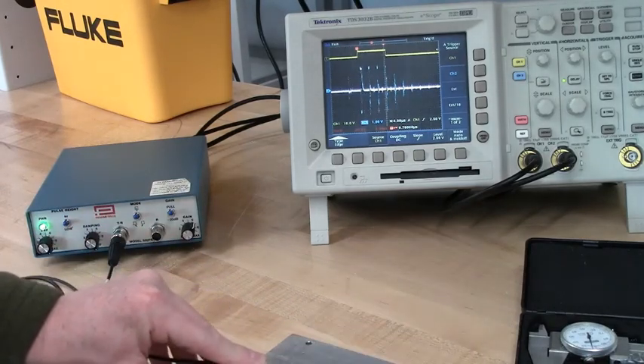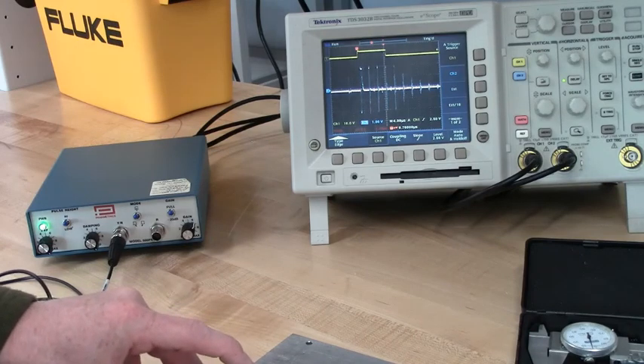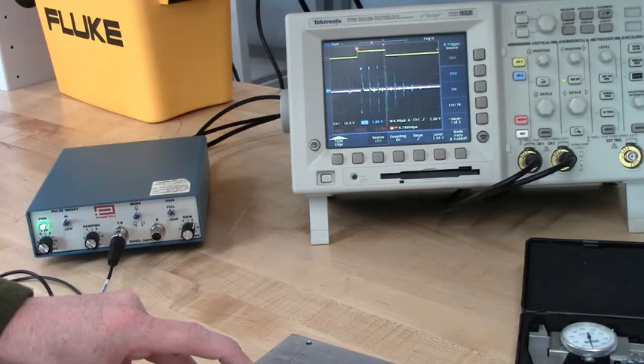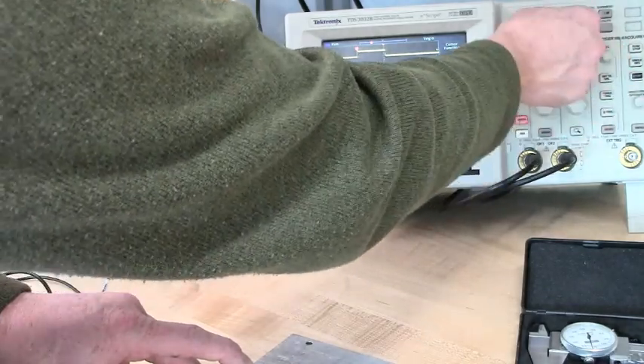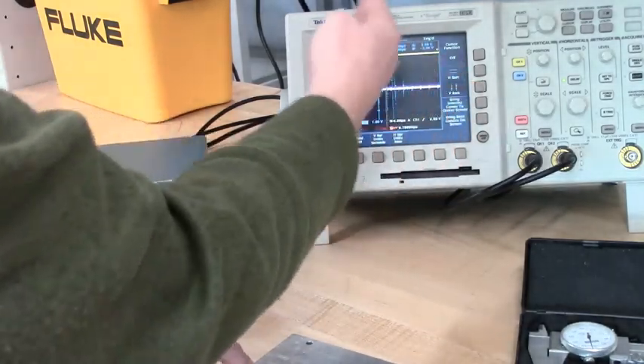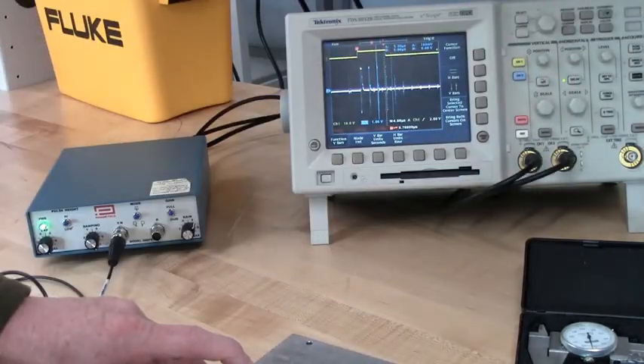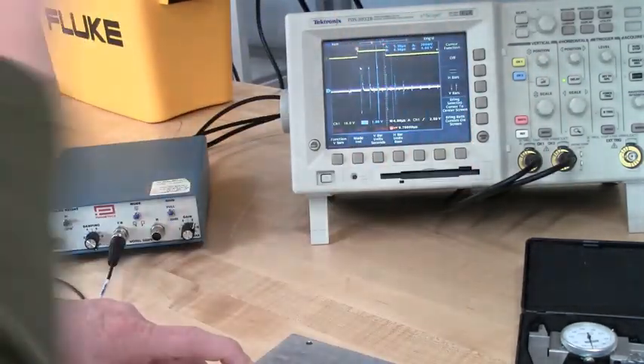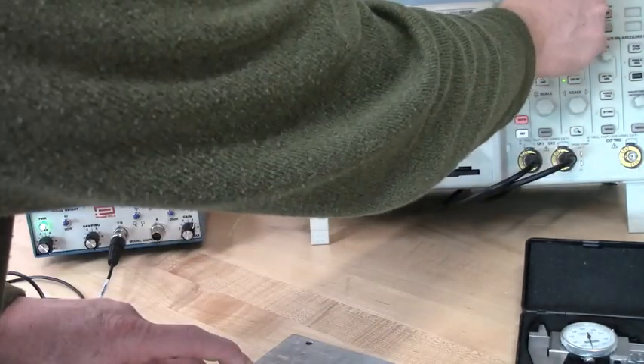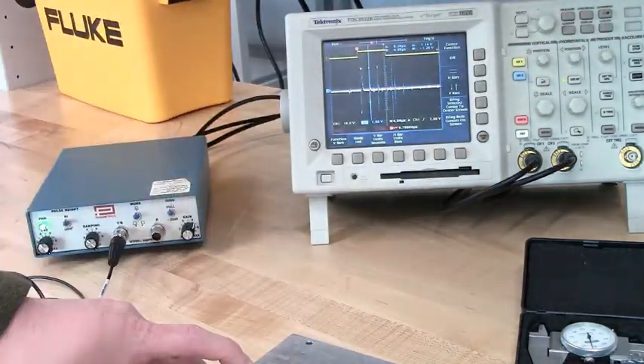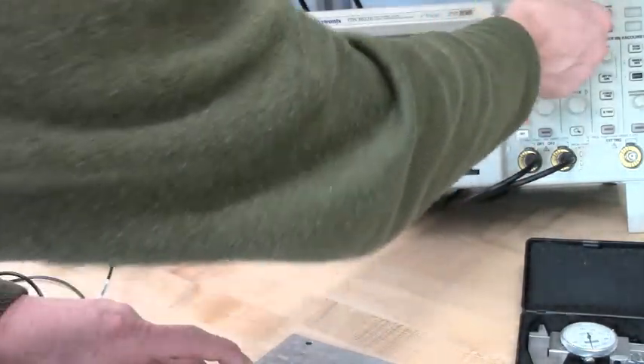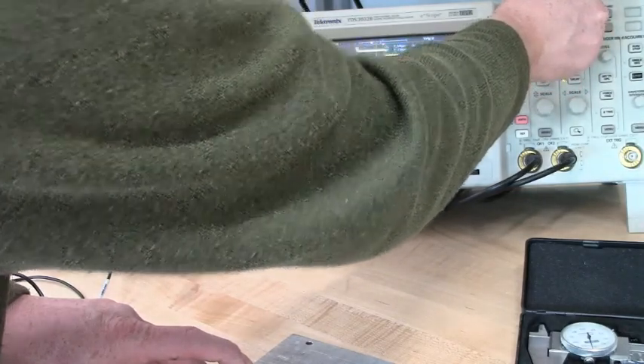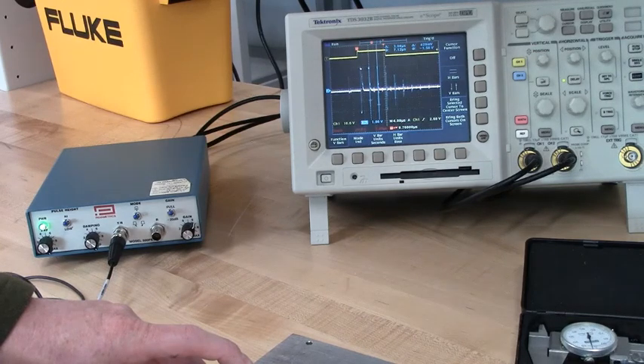So let's do that here. Let me get a good signal again. We're over the part that is of a known thickness that we can measure. There's nothing machined out of the backside of it. We have these pulses here. Let's use the cursor. My cursor is off right now. I want vertical bars, right? Vertical bars, I'll be able to measure the time between these echoes. So let me move one. We just move it to one spot in that echo, and then we want to move the next one. So we select that, and then we move the other one to roughly the same part on the next echo. So that was the time to go through and come back.